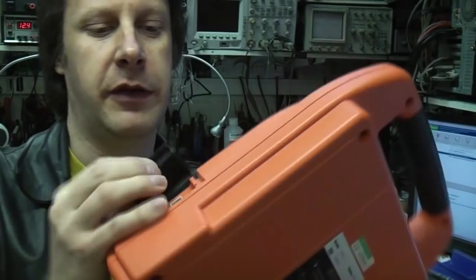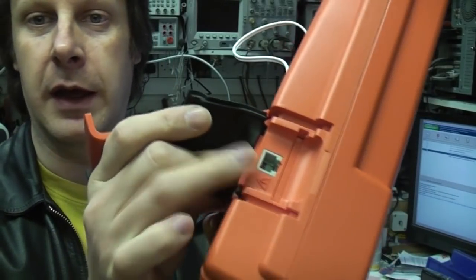Pretty much the only other external things here, there's a serial port here. This will be for downloading log data because obviously when this thing is working it'll be logging what it's doing, the waveforms, the decisions it's made, when it was used, how many times it's used. All that data can be downloaded as part of a monitoring program.